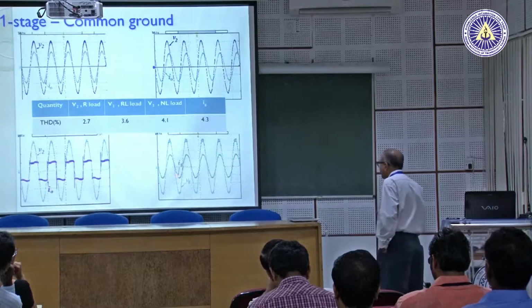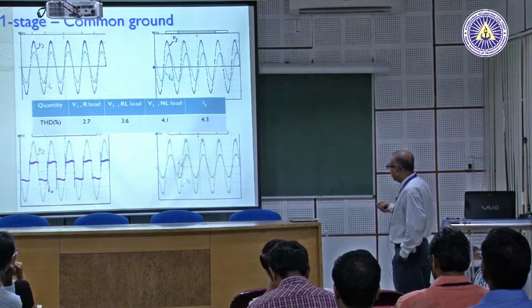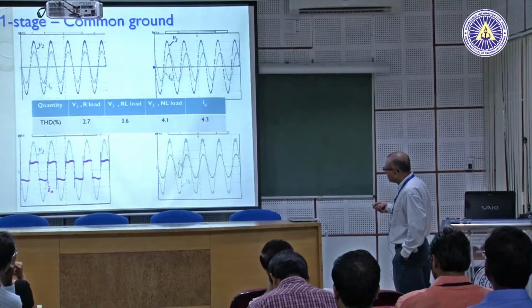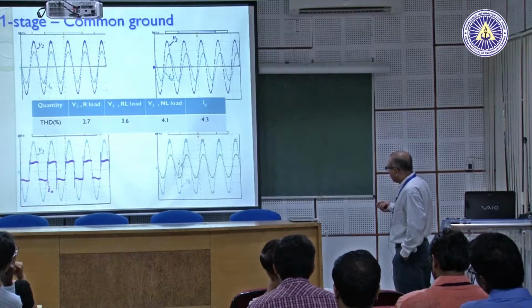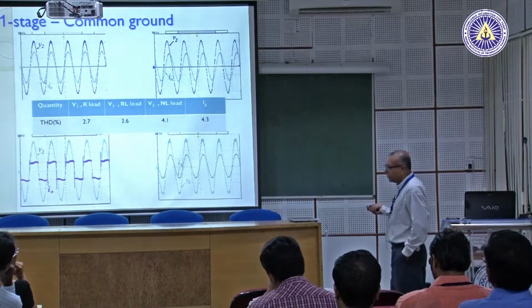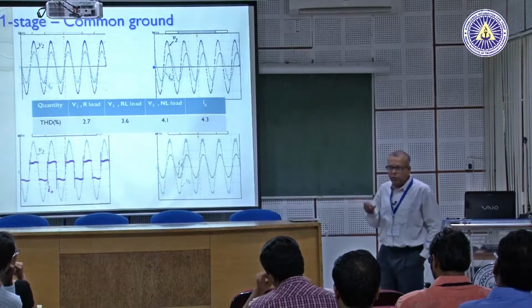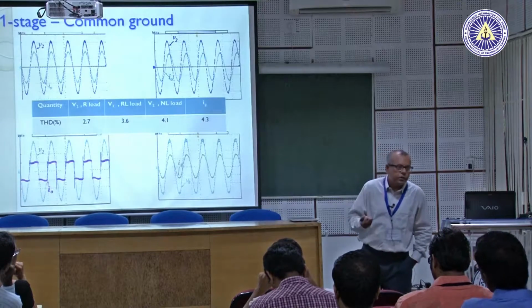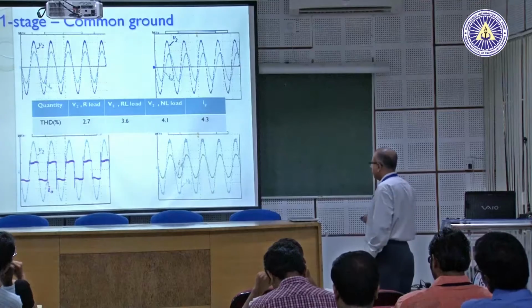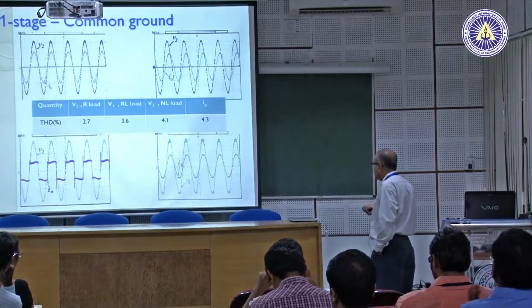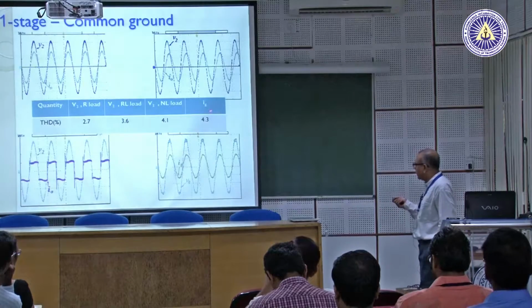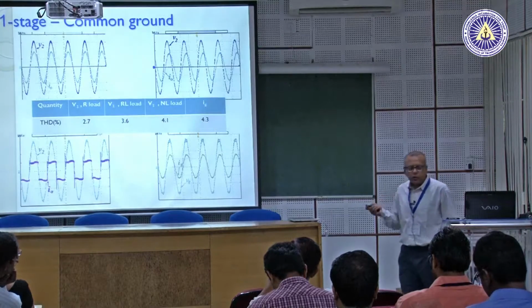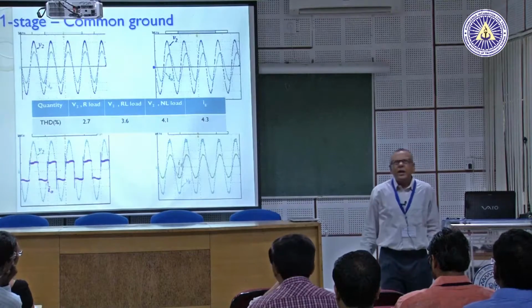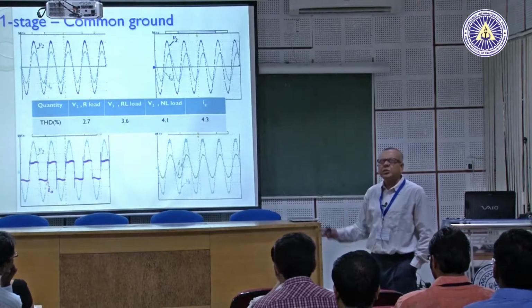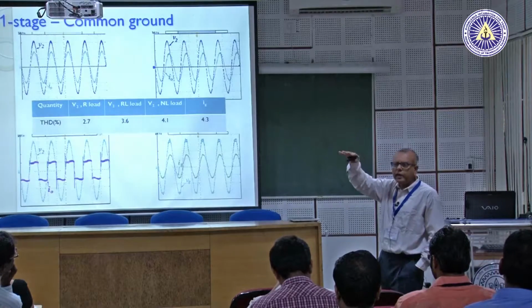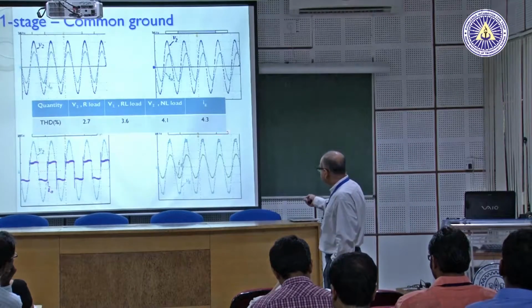And this is for the grid connected operation. By the way, this was the grid voltage, so you might appreciate that the grid was a little more nasty than the quality of the output voltage we produced in standalone operation. But even then we could manage to control the current with a THD around 4.3%. Again, the limits are, I think, about 7 or 8, I just exactly forget the number, so we are again well within these THD numbers.